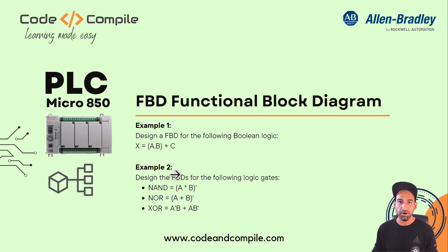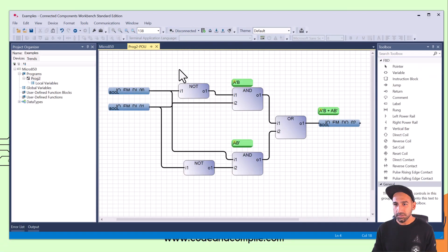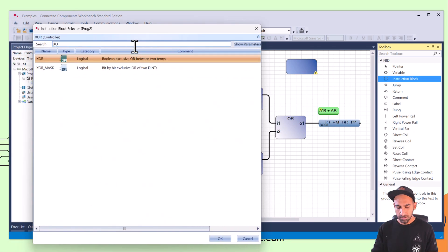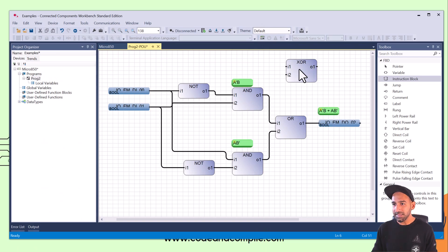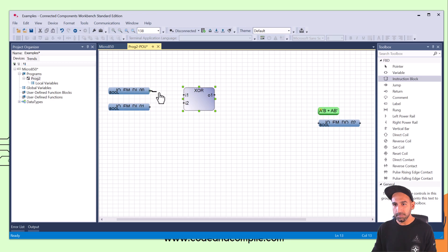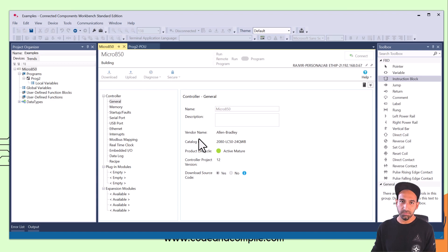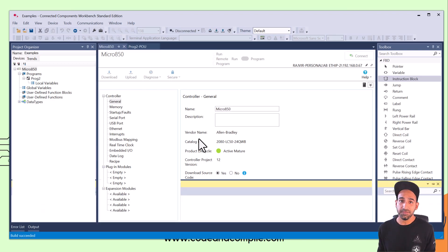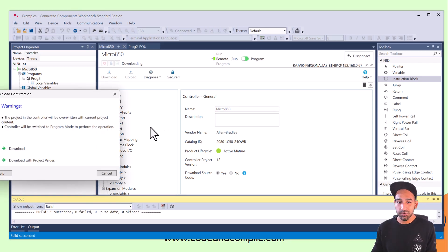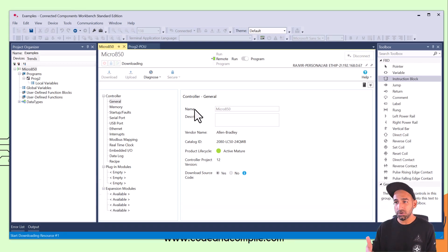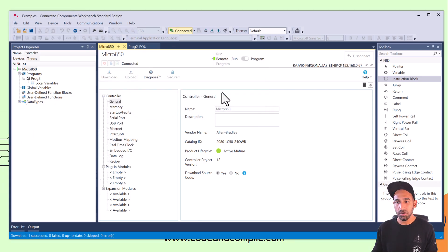This gate we designed ourselves using the Boolean expression, but you can also use a predefined XOR gate in this PLC programming. Let's see that right now — I'll take one instruction block and look for XOR or exclusive OR. That's my gate, and this gate has the Boolean expression predefined inside. So in this case you don't need all of that — just connect this gate. Allen Bradley has this function predefined in this block. And we're also going to learn how you can make your own predefined functional blocks. You can define any Boolean expression — like A dot B plus A dot B bar plus C dot D plus F — make the logic and compile it in one functional block, and just call that block.